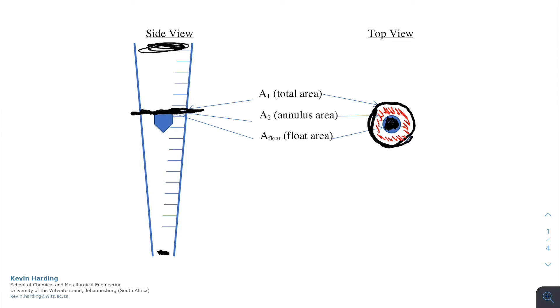Area A2, depending on where this float is sitting, is going to change as is the total area. If the float is at the top, there is a larger area of the annulus, whereas at the bottom there is a smaller area.